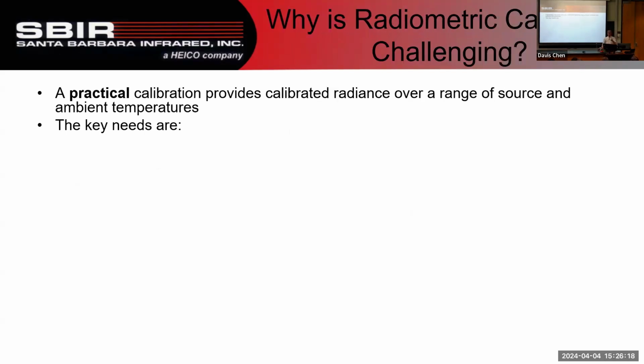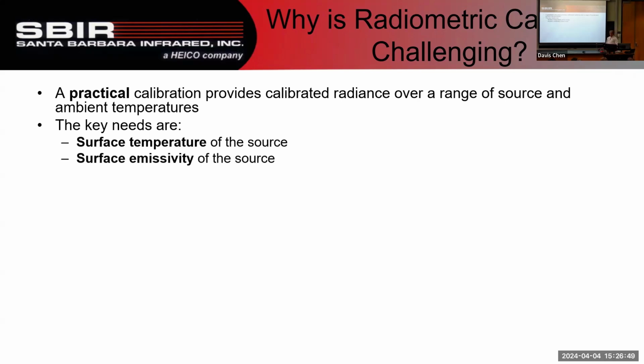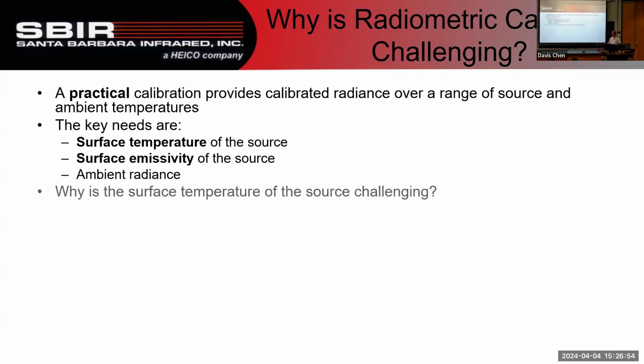So why is this such a pain? Well, one, it needs to be a practical calibration. It needs to provide calibrated radiance over more than just one source temperature and more than just one ambient temperature. Somebody's going to take this thing and put it in a lab somewhere, and you're not going to know what the lab temperature will be. And you can't just calibrate at one temperature on the black body because they run the black bodies over a huge range of temperatures. So I kind of cheated on my last slide, because what you need are the surface temperature of the source, the emissivity of the surface of the source, and the ambient radiance. And it's that surface temperature that's a pain, right?